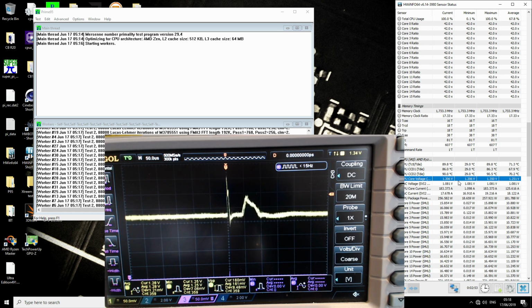So then at 20 amps, it's supposed to be drooping 16 millivolts, I want to say. So at 20 amps, it's supposed to be at, say, 1.32 volts or 1.33 volts. And as long as the peak of that spike is not higher than 1.33 volts, then we're technically in spec.